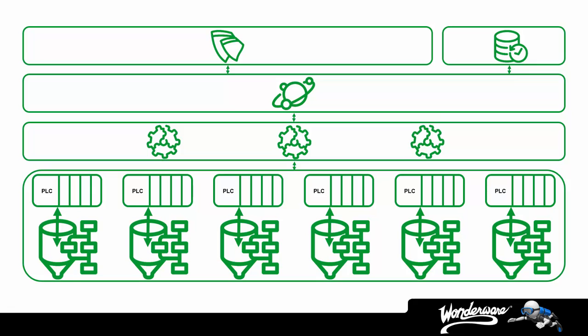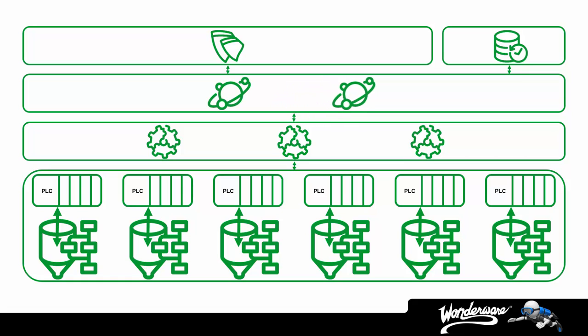This is where application server adds even more advantage. It can detect that communications have failed and automatically reroute communications through another device access server. As this places the application server component as the sole source for all data to the historian and the HMIs, it probably makes sense to distribute the application server components across more than one computer as well. You see, app server can scale from a single computer to 2, 5, 10, 50, 100 or whatever you want. This scaling allows the pieces of application server to be distributed across nodes and provides redundancy between those nodes.